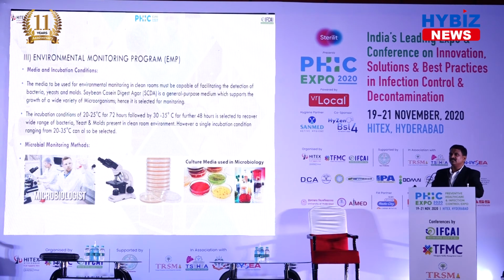However, dual temperature incubation, that is initially lowest followed by highest, is the ideal scenario, wherein all types of microorganisms can be recovered, and moreover the area which we are monitoring has a temperature range of 20 to 25. If we incubate at the same temperature, with favorable conditions, the injured microorganisms, if any, will be recovered.